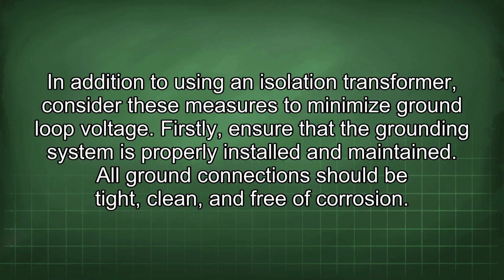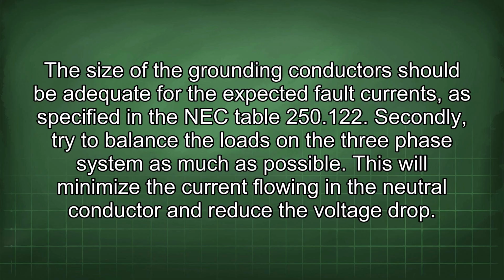In addition to using an isolation transformer, consider these measures to minimize ground loop voltage. Firstly, ensure that the grounding system is properly installed and maintained. All ground connections should be tight, clean, and free of corrosion. The size of the grounding conductors should be adequate for the expected fault currents, as specified in the NEC table 250.122. Secondly, try to balance the loads on the three-phase system as much as possible. This will minimize the current flowing in the neutral conductor and reduce the voltage drop.